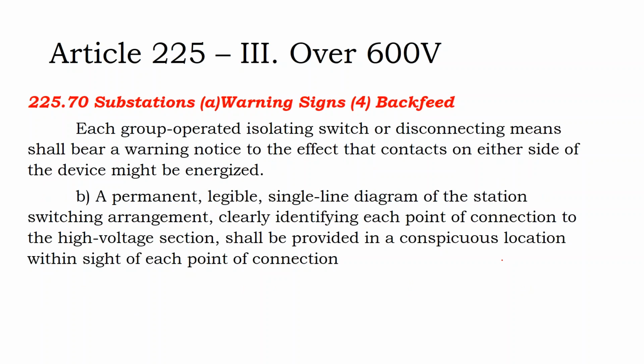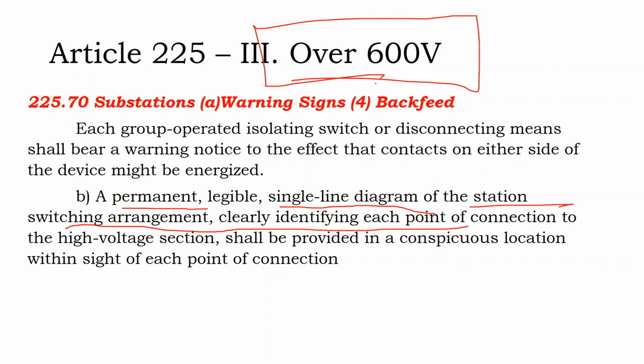Substations, you know, here we have requirements for not just a plaque indicating where feeders are coming into the building, but a plaque that says you have to have a permanent single line diagram of the substation that lets someone know where they're going on. And this is just an example of, you know, if you're in a behind the fence over 600 volt project, there may actually be more requirements for you rather than fewer requirements to abide by. You know, not just putting a directory of where the power is coming in and out of the building, but also a simplified electrical diagram that can tell the inspector what's going on.